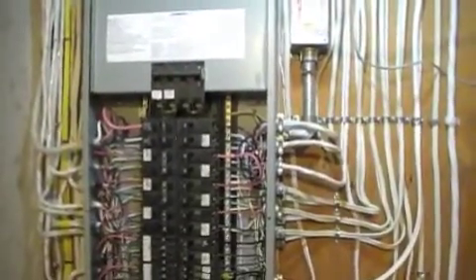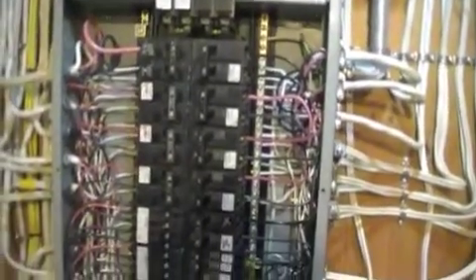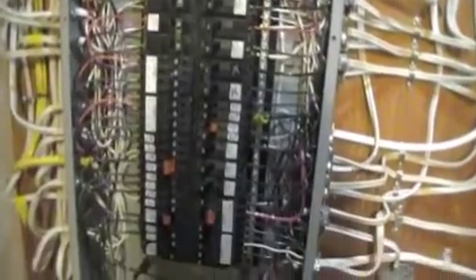That's the panel inside. There are breakers and wires. Here, this silver-colored bar on the right-hand side of the breakers, and the same on the left-hand side — these are neutral bars. Their purpose is return of current. They will have a potential only if any one of the devices is working and current is returning to the panel after visiting light bulbs or receptacles with working equipment.